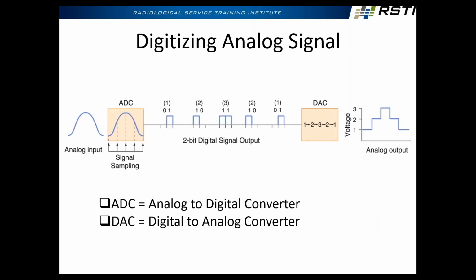If you look at an ultrasound image, there's a lot of black, there's a lot of white, there's not a lot of contrast in the middle, right? They're very high contrast because you have your white up here, your black here, and you've got 256 different shades of gray. Well, if you had a 9-bit A to D, how many shades of gray would that give you? 512. 10-bit, 1024. 11-bit, 2048. 12-bit, 4096. And let's call it 8K and 16K. So 14 or 16-bit is what a mammo or a DR rad room would use for A to D converters.